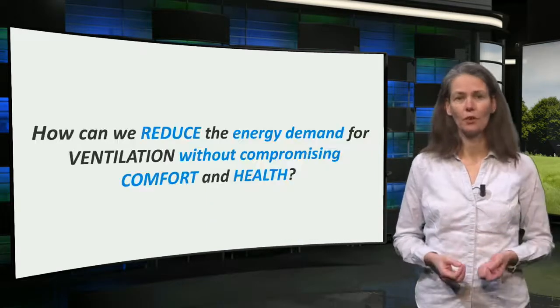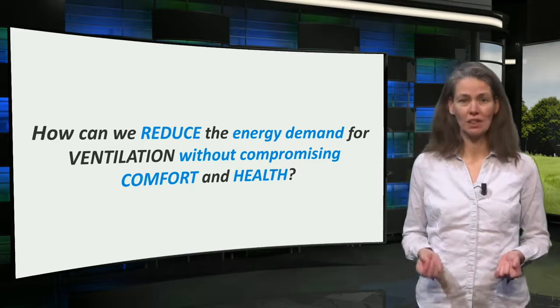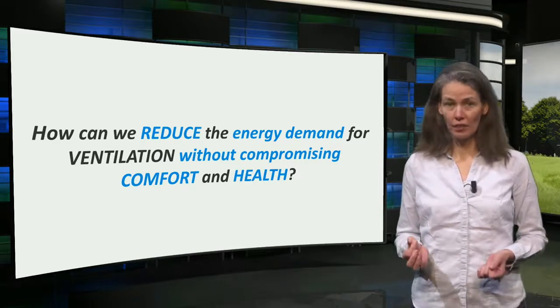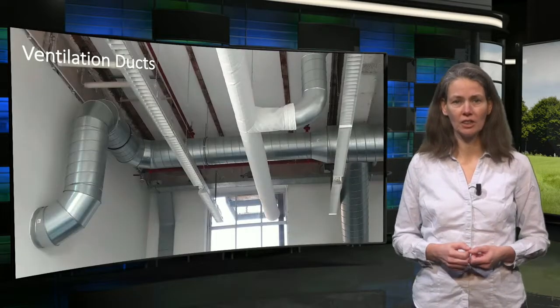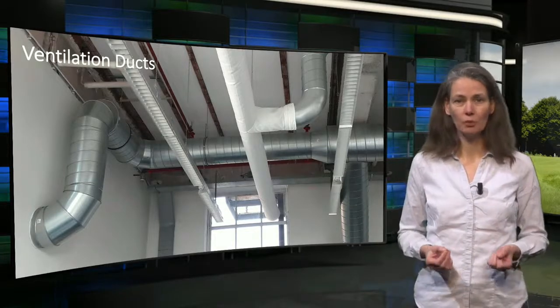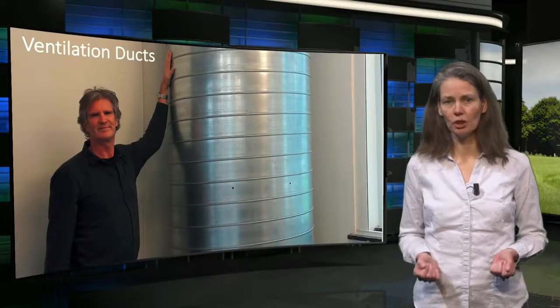How can we reduce the energy demand for ventilation without compromising comfort and health? The energy demand of moving the air in and out of the building depends on the efficiency of the fan, the length of the ducts, the amount of bends, and the speed of the air. A wider duct at the same amount of air is therefore the best option to move air into or out of a building.